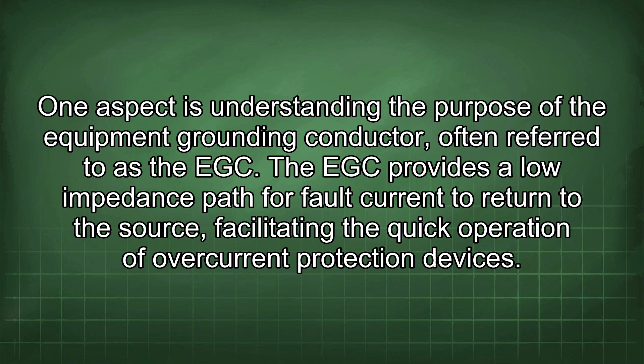One aspect is understanding the purpose of the equipment grounding conductor, often referred to as the EGC. The EGC provides a low impedance path for fault current to return to the source, facilitating the quick operation of overcurrent protection devices. The size of the EGC is determined by the size of the overcurrent protection device protecting the circuit, as specified in NEC Table 250.122.